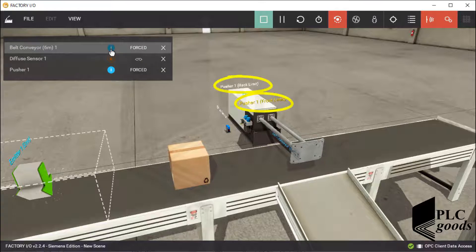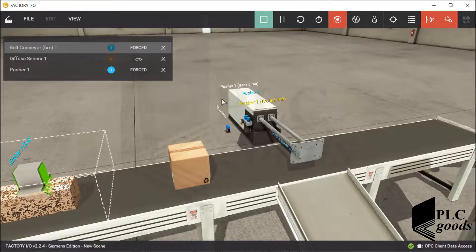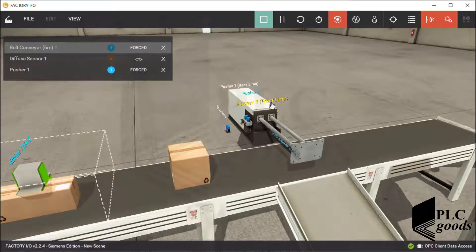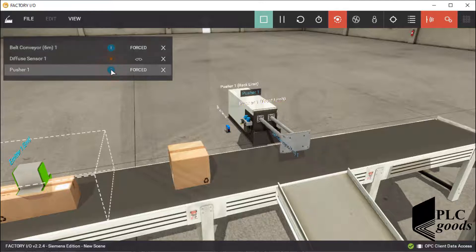Note that the pusher has two sensors to detect its state. When the pusher arm is fully extended, the sensor with the tag 'pusher front limit' will be one. I will use a rising edge trigger inside the PLC program to detect this change, because after this state the pusher must be turned off.